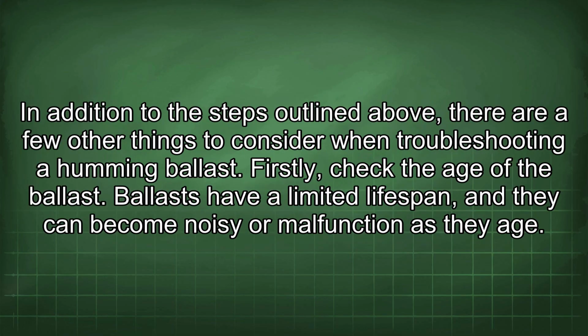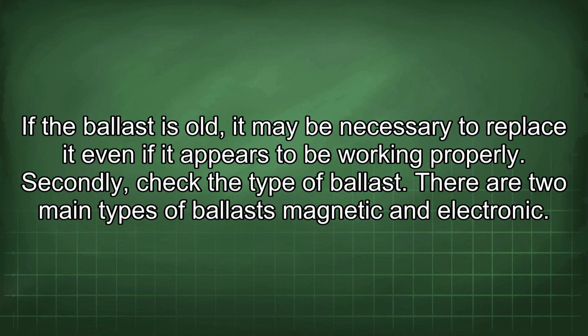In addition to the steps outlined above, there are a few other things to consider when troubleshooting a humming ballast. Firstly, check the age of the ballast. Ballasts have a limited lifespan, and they can become noisy or malfunction as they age. If the ballast is old, it may be necessary to replace it even if it appears to be working properly.